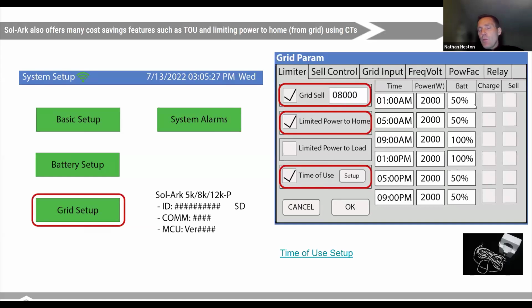If the battery is below 50%, as soon as the battery gets up to 50%, it would stop. So if I click the charge box, that's what would happen. If I have the sell box checked, it will also sell excess battery power until the battery gets down to 50%, right?